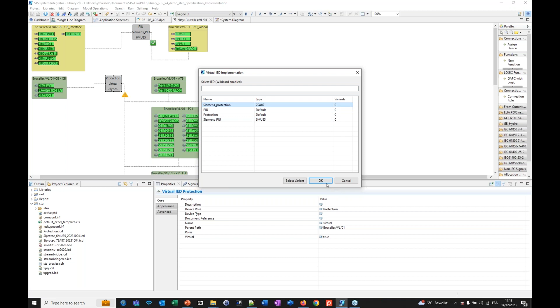Then I can also show you, for example in the PIU here, all the structure defined in the specification and the structure where it is implemented. If you see this example, for instance, we have all the logical nodes in the PIU global implemented within a logical device PIU global in this ID, except this one, because probably in this process ICD file, the step done by Cedric just before, where the same logical device structure was defined, was not done for this one. Then you can quickly also see if your specification and your implementation fit one-to-one.